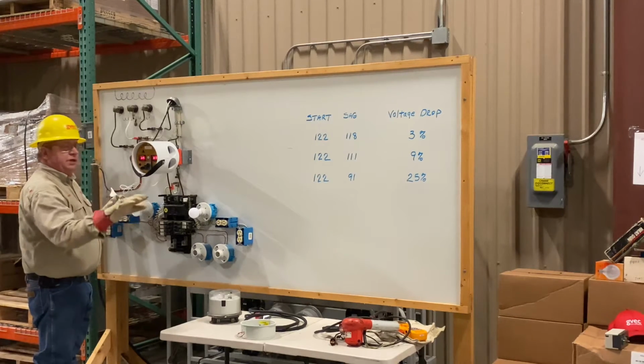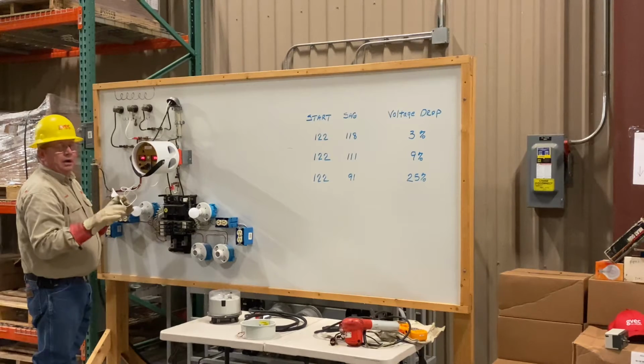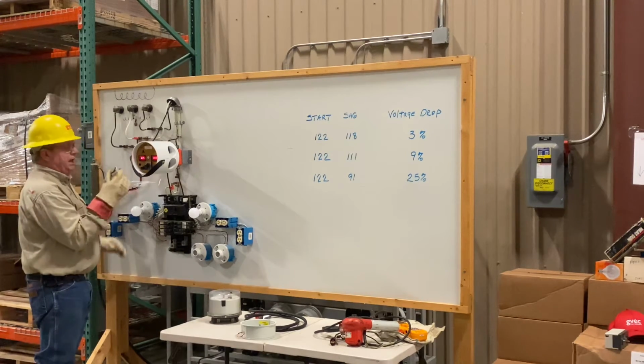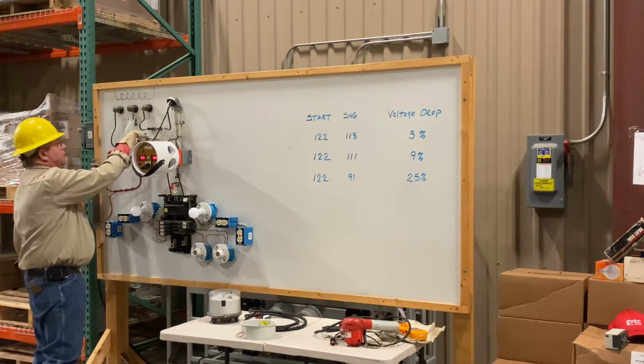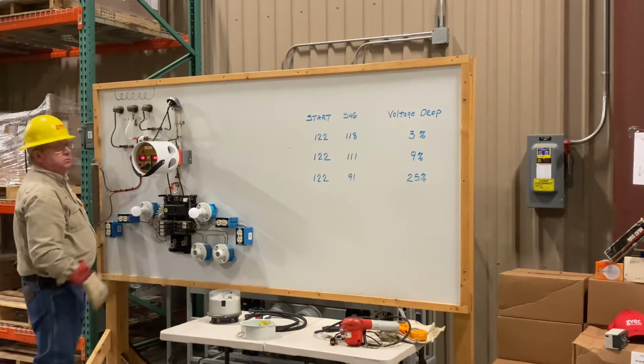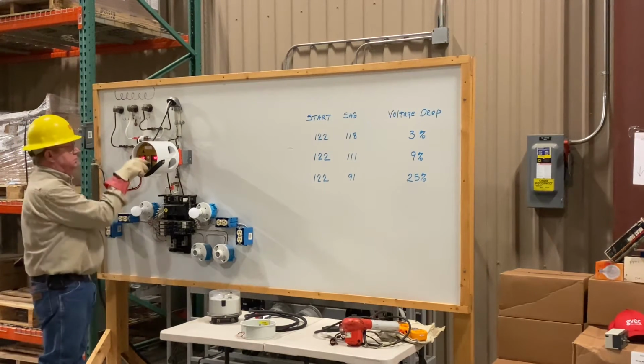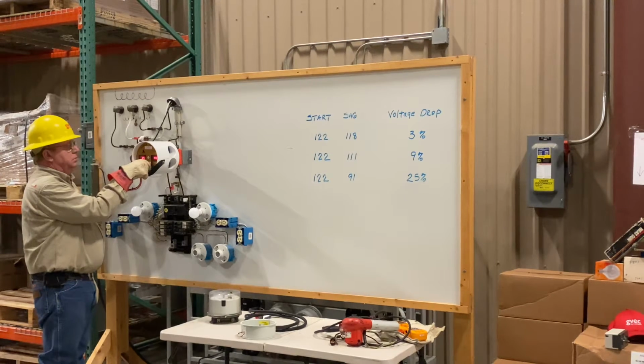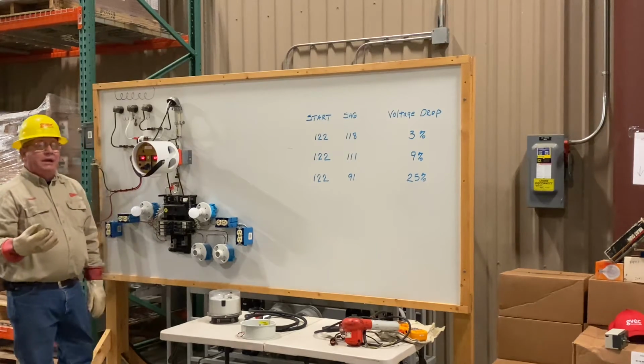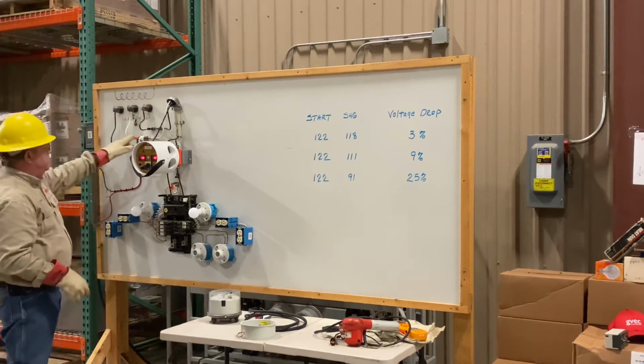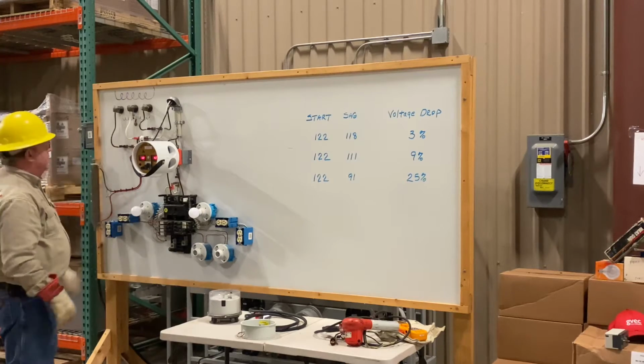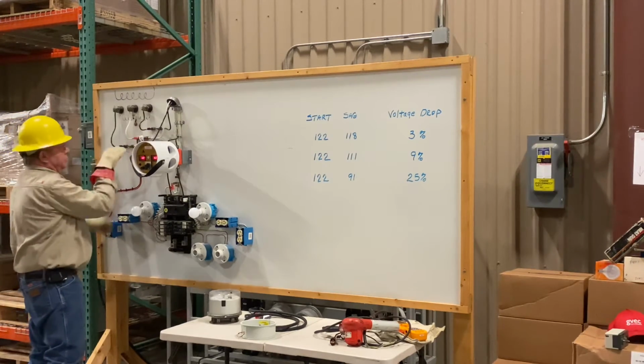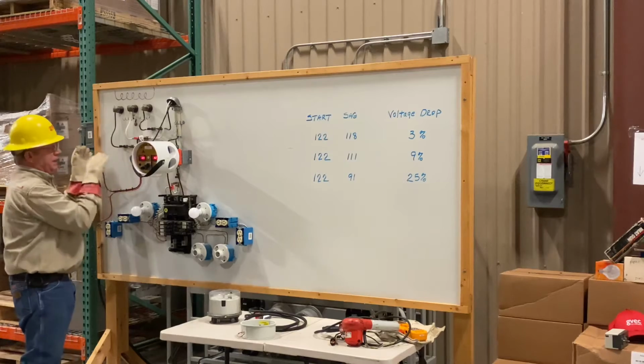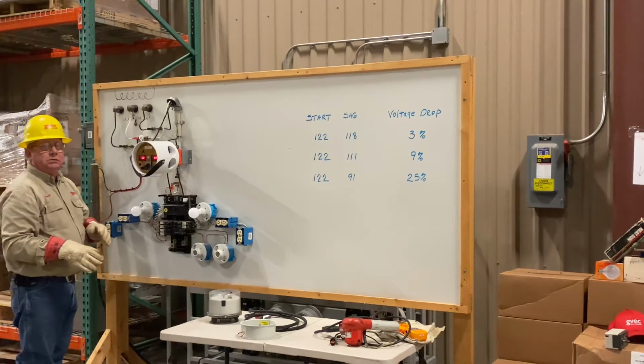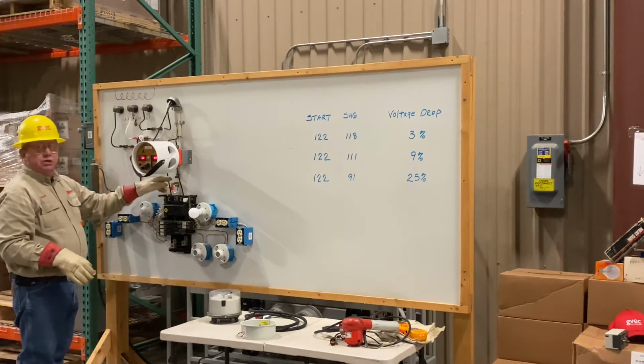The neutral connection going into her house is broken. When it leaves the disconnect panel underneath the meter, that wire is broken. But we're going to connect it over by the transformer. Voltages are balanced. We don't see a bad connector because of where we put the neutral connector. Now I'm going to put it, this neutral connector and this meter cannot see down line. So it has no way to know that this neutral is broken.